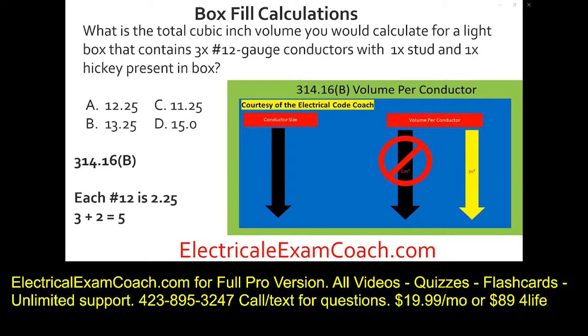That's what I meant by we're converting everything back to conductors, and then we can do our multiplication. We take those 5 number 12s, multiply by the cubic inch volume for 12, and we end up with 11.25 cubic inches, and we would select C.